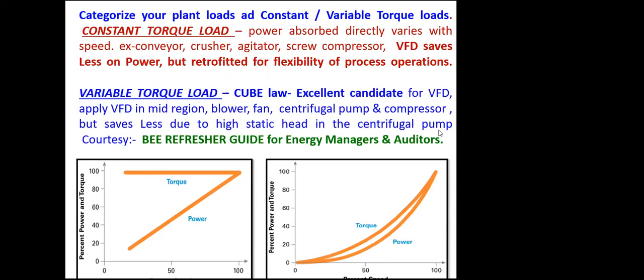So when you are getting ready for the energy audit in your industry, categorize your loads. You can discuss with your OEM also. What are your constant torque loads? What are your variable torque loads? For constant torque loads, as speed varies from 0 to 100%, the torque stays constant. Most of your production machines will be constant torque loads. Most of your variable torque loads will be on the compressors, centrifugal compressors especially, even axial flow fans to some extent, and centrifugal flow pumps to some extent.